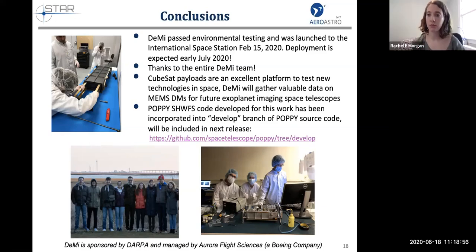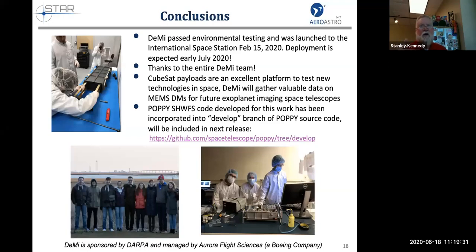So before and after every test, and during all of environmental testing, we took measurements where we first took a picture of the spot field on the Shack-Hartmann and the image plane wavefront sensor. That way we could tell whether anything had shifted during these tests. We also did a poke test, where we poke every single actuator and measure the deflection, and we keep track of the deflection measured over time for each actuator. The question was, especially with the actuator throw or position accuracy, was there repeatability there, or did you see bias or any kind of shift during those?